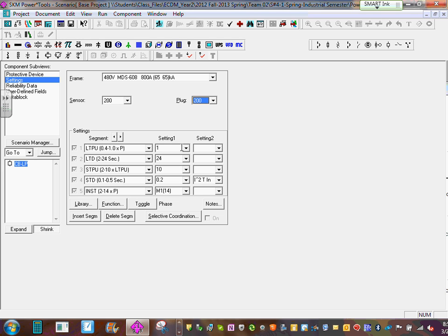Okay, do me a favor. You need to set them up. So I need 175. Take 175, divide by 200. What's the percentage? 0.875, like 0.88. So I need to set this one at 0.88. I don't have 0.88. So what do I have? 0.9. So I got very close to 0.9. So I set it up at 0.9. Done. Did you guys see that?